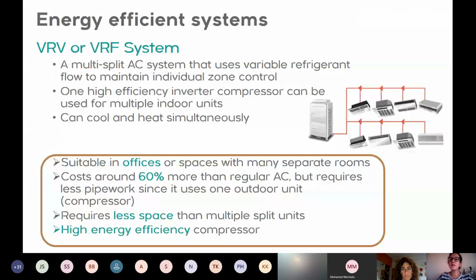The other type of system is called a VRV or VRF system. The idea here is it's a multi-split AC system - basically one compressor or one outdoor unit connected to several indoor units, meaning one outdoor unit serving several indoor spaces. This outdoor unit is also a high efficiency inverter compressor, so not only are we saving space, but we are also saving in terms of energy.